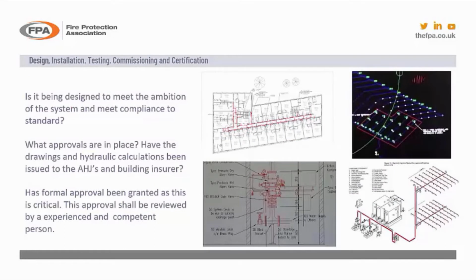So, moving on to key stage 2. Once we've got the specification right, we've selected the right tenders, we know what standard we're going to work to, we know the classification of the system, we know what water supplies requirements, is it going to comply? All these little key issues, we move then on to when it goes into design, installation, testing, commissioning, and then obviously the final certification. So this takes you, our stage 2, through what we would expect everybody to follow to ensure that the sprinkler system is maximised to its potential and complies.